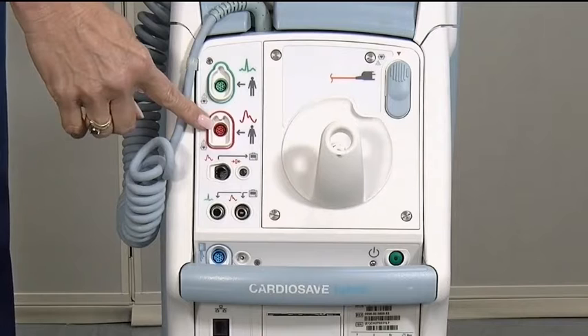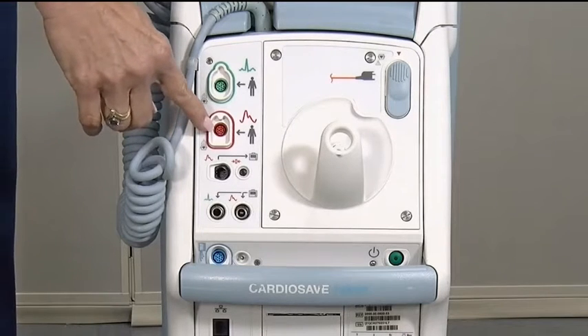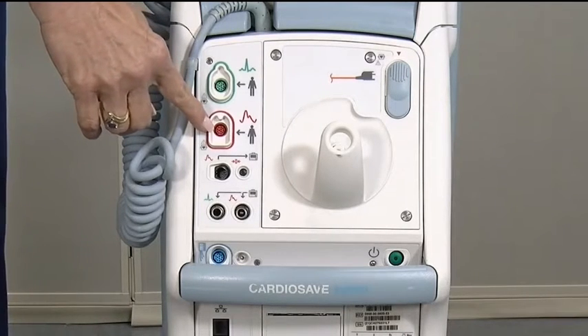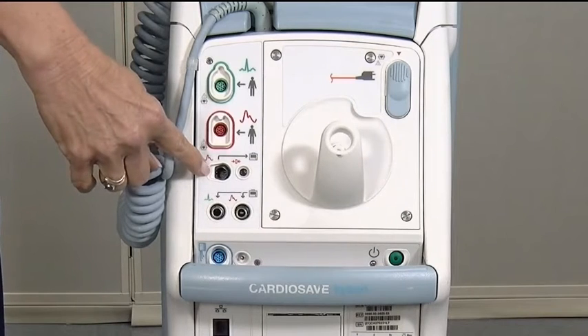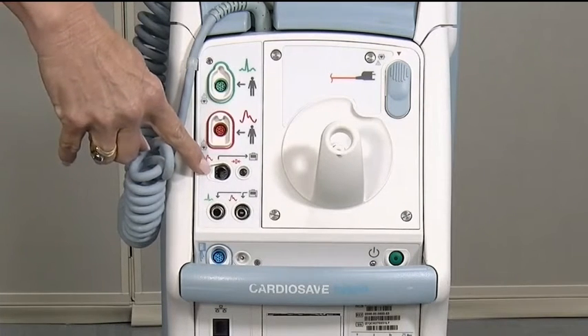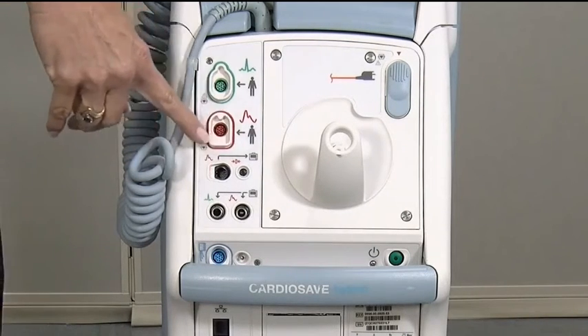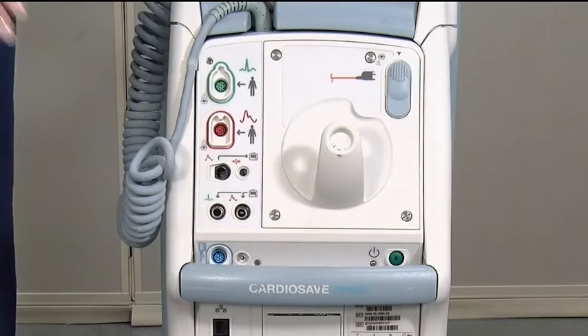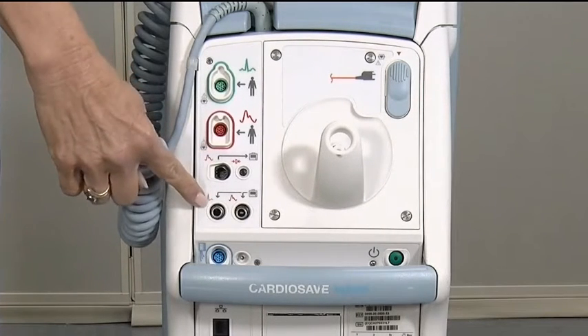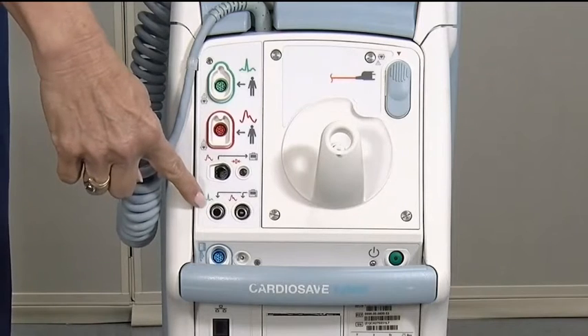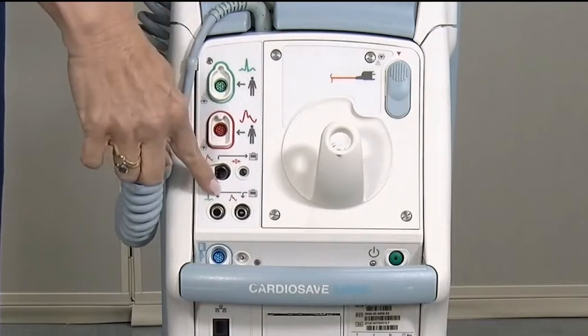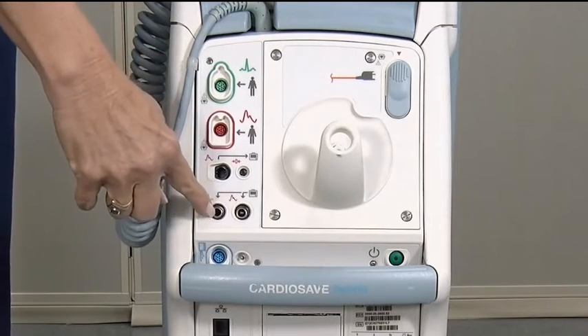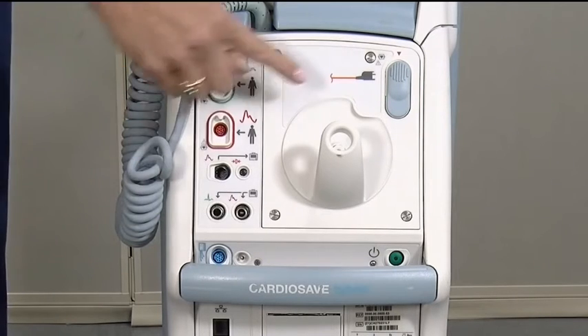Beneath that is where your pressure input is. It is also color-coded and keyed and is specific to the CardioSave pump. Moving down, this is a low-level output. The low-level output allows you to take the signal from the balloon pump and put it to the bedside monitor. Beneath that are radio jack inputs. This takes the signal from the bedside to the balloon pump. You can do both pressure and ECG there.